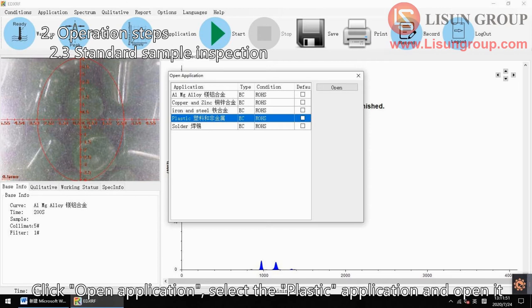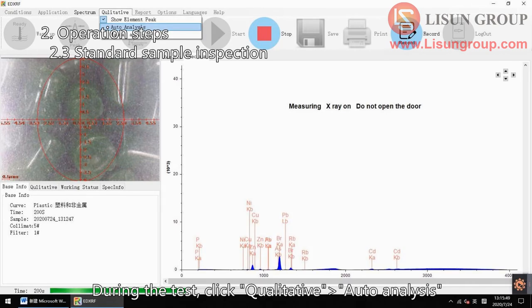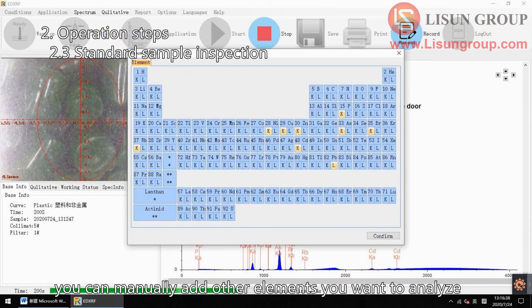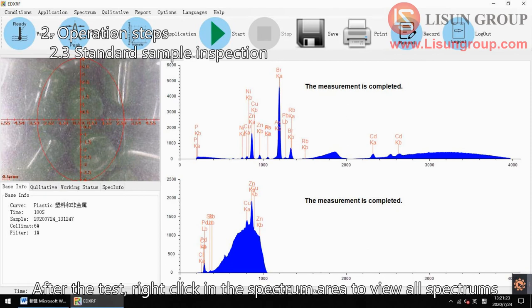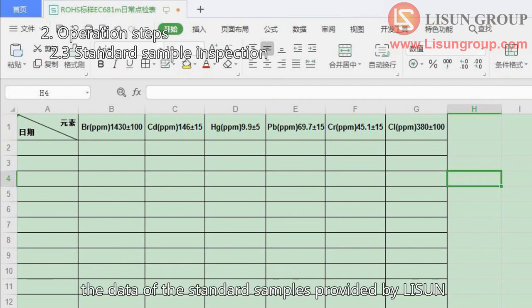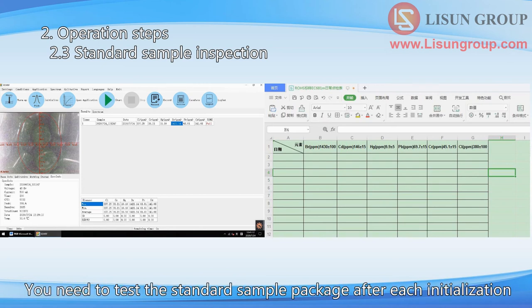Click open application, select the plastic application and open it. Then click start. Enter the sample name and click confirm to start testing the standard sample. During the test, click qualitative auto analysis to automatically analyze the elements and content of the sample. Click qualitative manual analysis if you want to manually add other elements to analyze. After the test, right click in the spectrum area to view all spectrums. Switch to the test result table to view the content of each element. Compare the data in this table with the data of the standard samples provided by Lisun — the error within the range proves the equipment is in normal condition. If the error is out of range, please contact us. You need to test the standard sample package after each initialization.